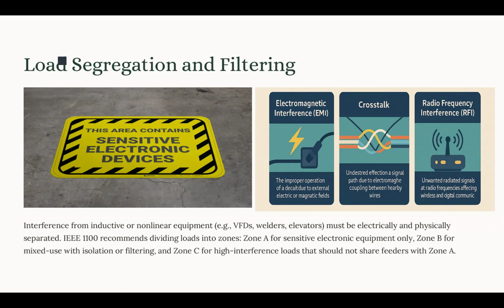One would be they have to be completely separated. They have to have completely separated feeders and panel boards. So they should not share any feeders, transformers, or neutrals with zone A. Okay. They have to have active or passive filters at the sources that contain noise for harmonic mitigation, basically. And they have to have physical separation, meaning the cables routed away from the zone A circuits should be separated so we could reduce the inductive or capacitive coupling between the cables that feed zone A and zone C.